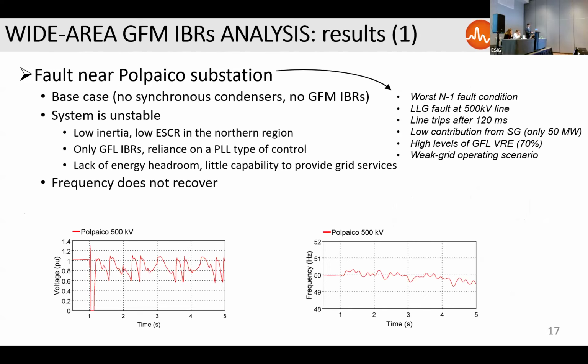All right, so the first test was to simulate a fault near a substation, which is called Polpaico. And this location is the worst in the sense that faults here oftentimes lead to an unstable grid. Depending on your operating conditions, if you're operating close to the transmission limit of the 500 kV transmission, it may lead to complete loss of the grid. If you are below the peak, it will lead to the largest swings in the generator angles. So, a line to ground fault at the 500 kV line is isolated by disconnecting the faulted line. And here at the bottom, you see the results of the voltage amplitude and the frequency measured by a PLL. You can see that the frequency basically becomes unstable. The grid is not recovering after the fault.